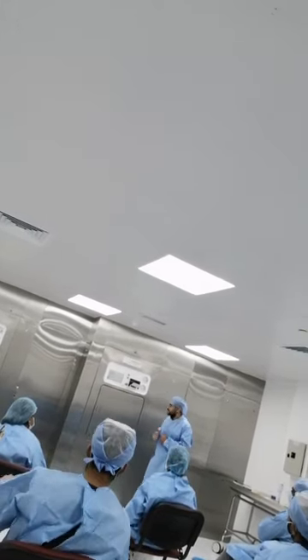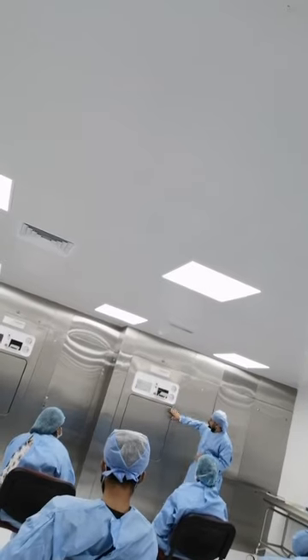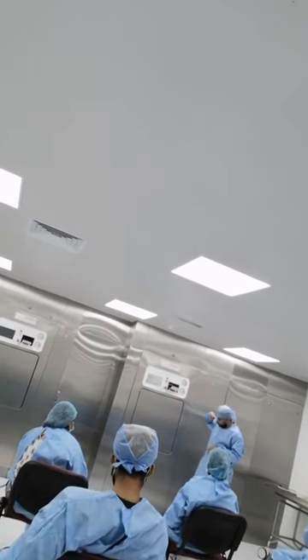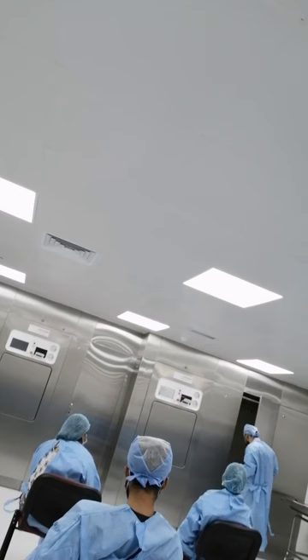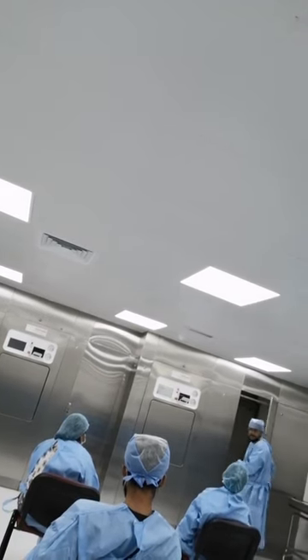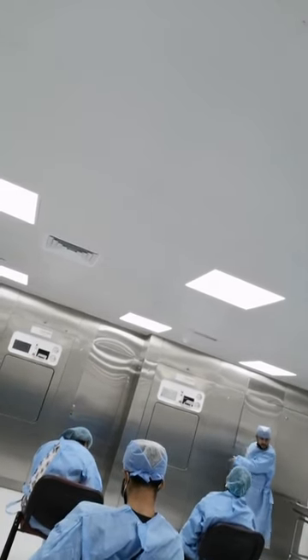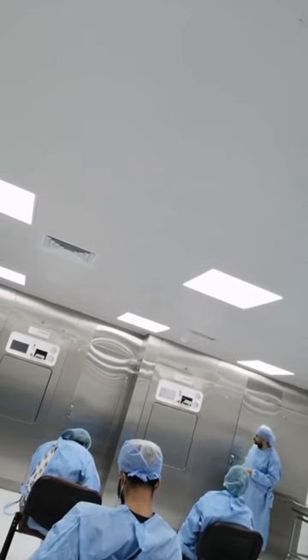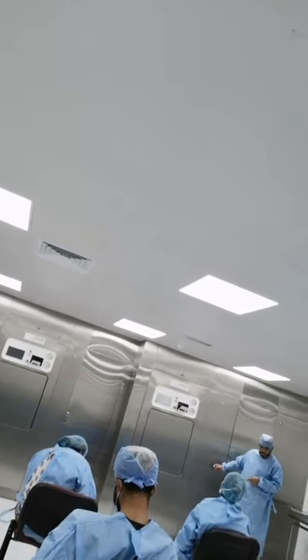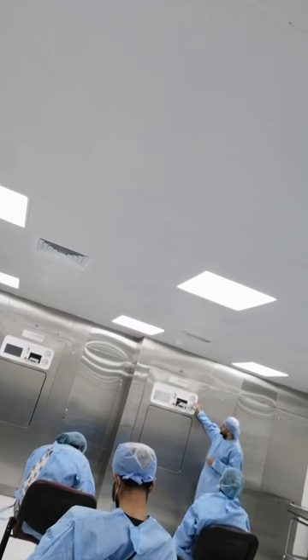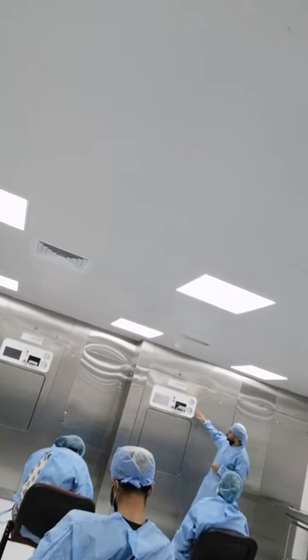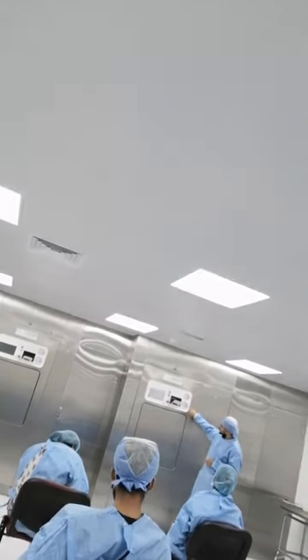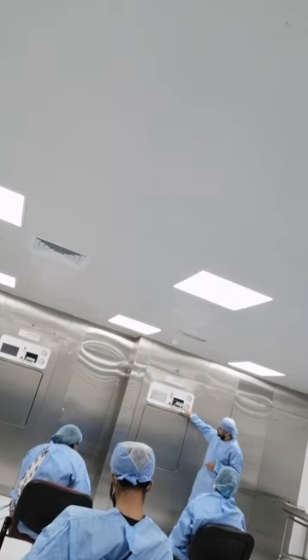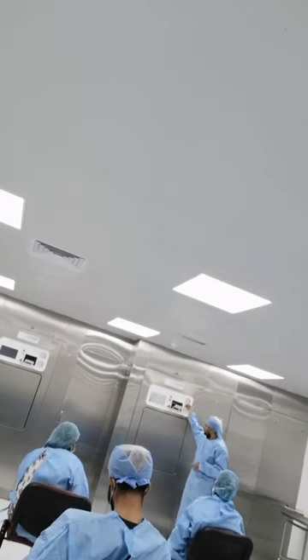Okay, so let's talk again about operational aspects. On this machine we have here, the source of steam is a built-in steam generator. Okay, the steam generator is 50 kilowatts, and it has to operate at 2.7 to 3 bars. And then this is the pressure of the chamber, and because there is no cycle running, it is zero.